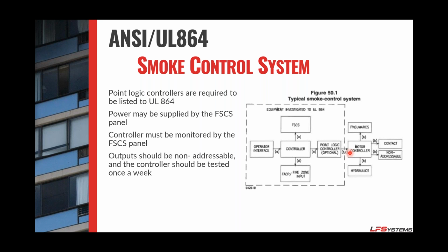If it's just a dumb device doing what it's told, like a VFD typically does, it takes in a signal from a control that says, I want to run at this speed. VFD, do what you're told. It does what it's told. That's a non-decision making device, so therefore it does not have to be listed. But the device telling it what to do does. That is the definition of a point logic controller. It is logically controlling something based on points of information, and that does require a listing.